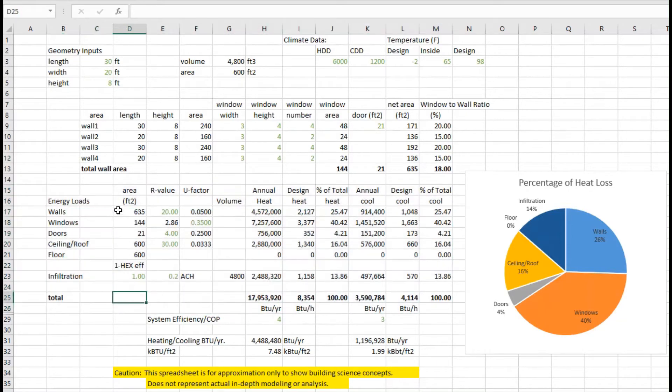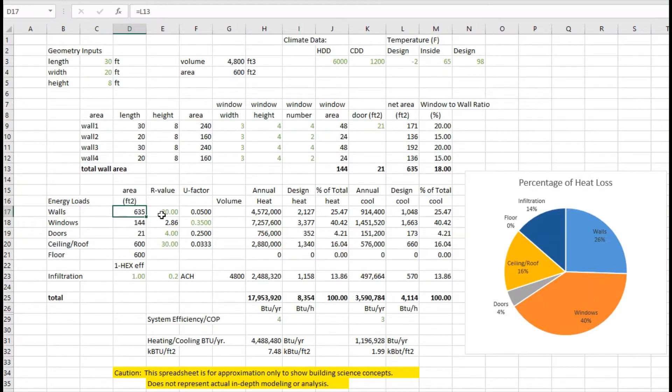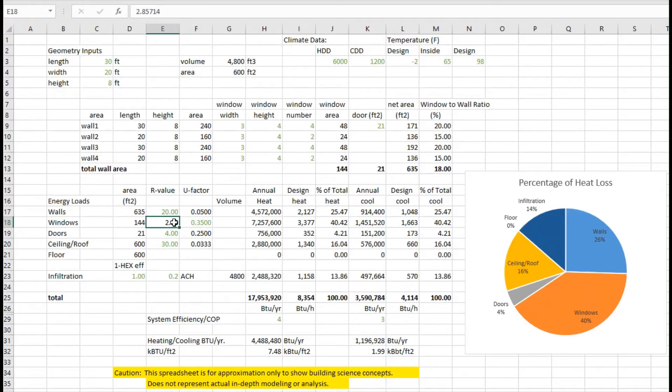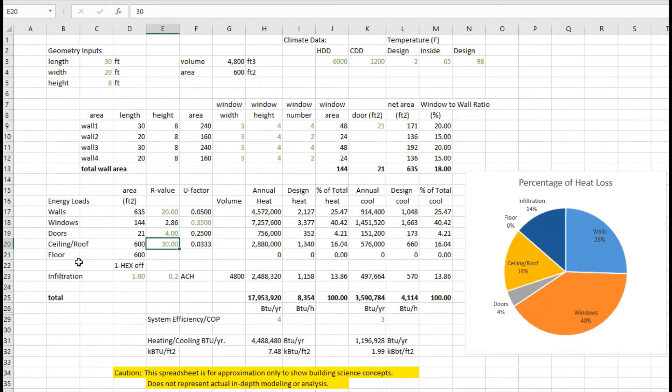We take the area that we had calculated up above, and I'm going to add the R value. So I've got an R value for the walls, and from that I can compute the U factor. Usually for windows we have the U factor, so I can calculate the R value from that. We've got a door with an R value of 4, we've got some ceiling roof, and I'm still going to ignore the floor for the time being.